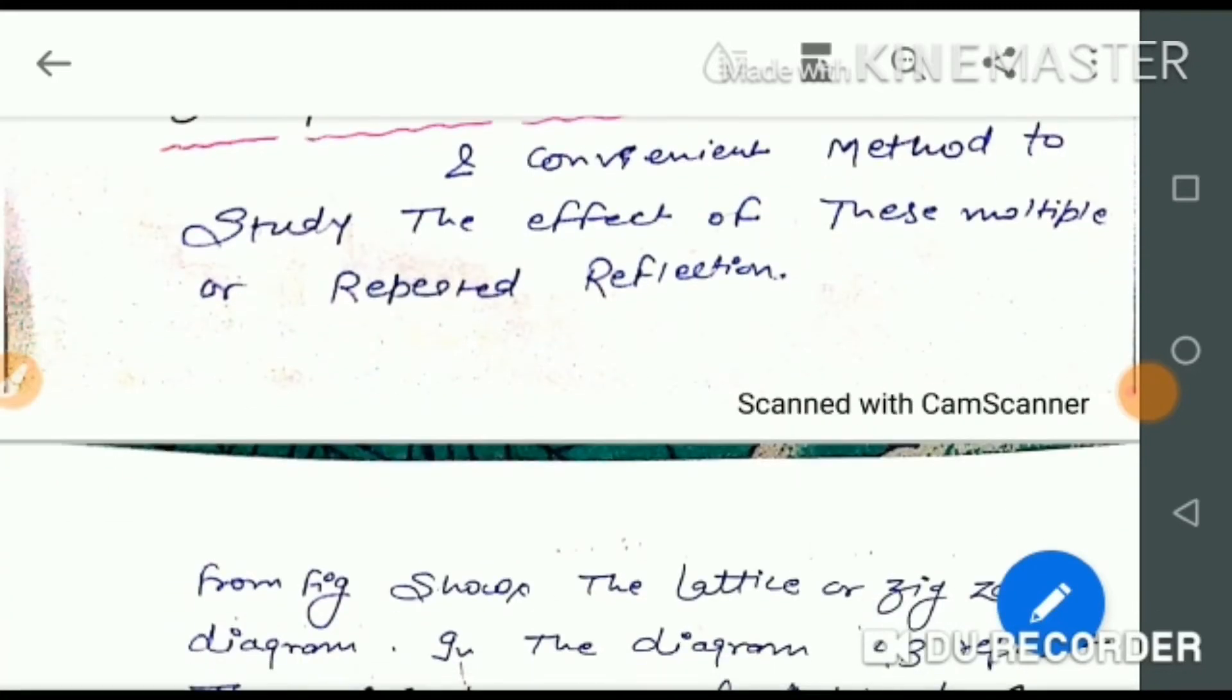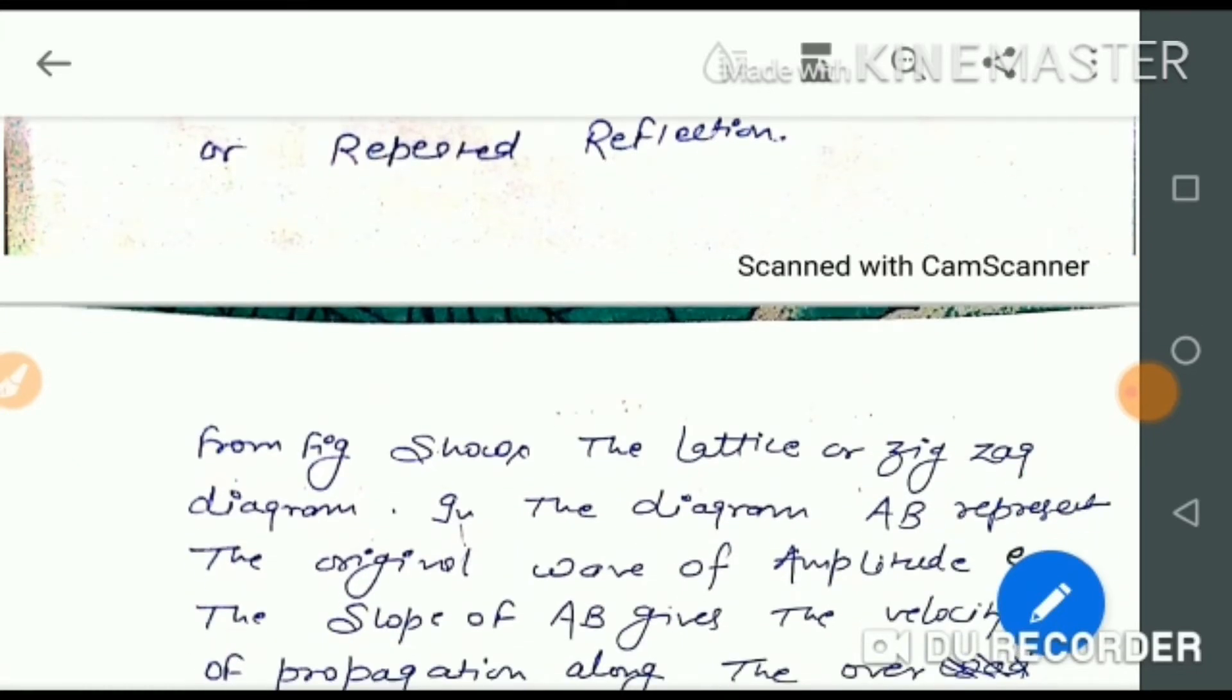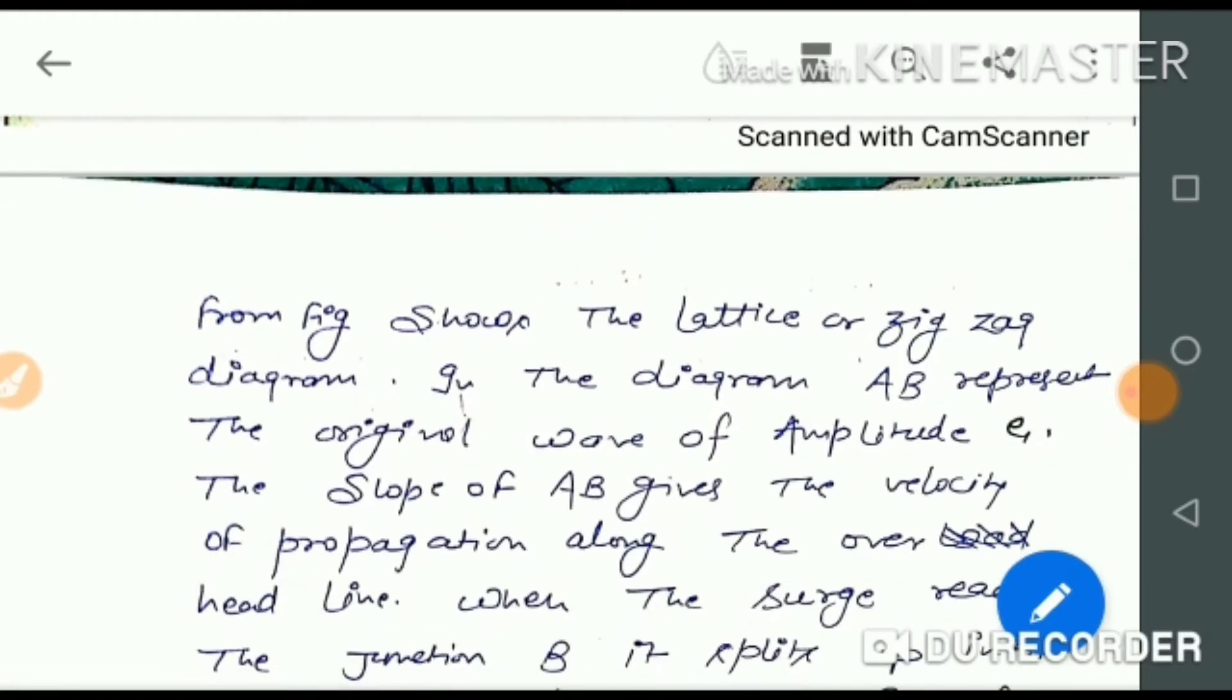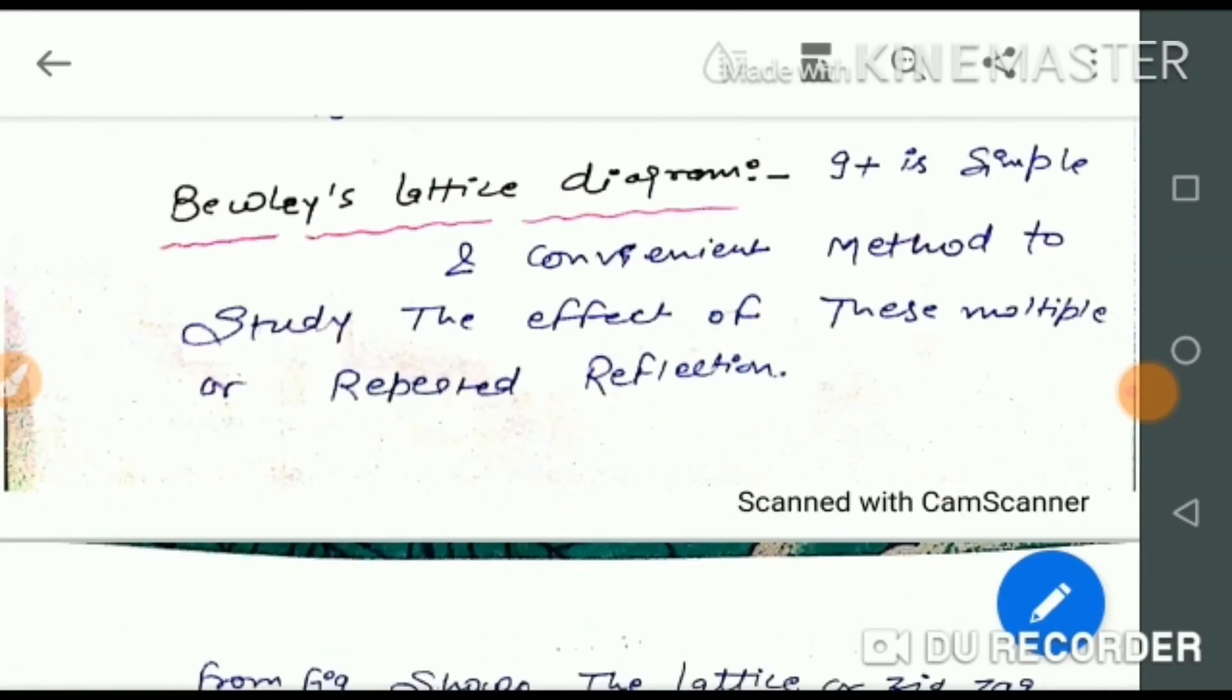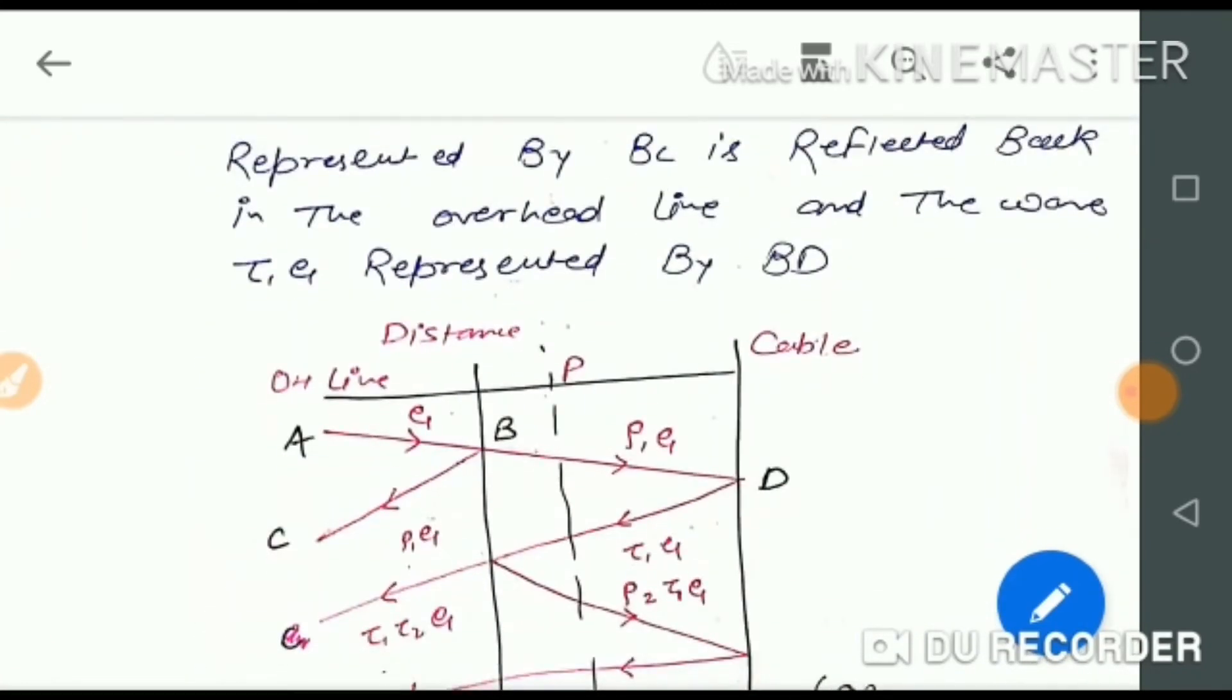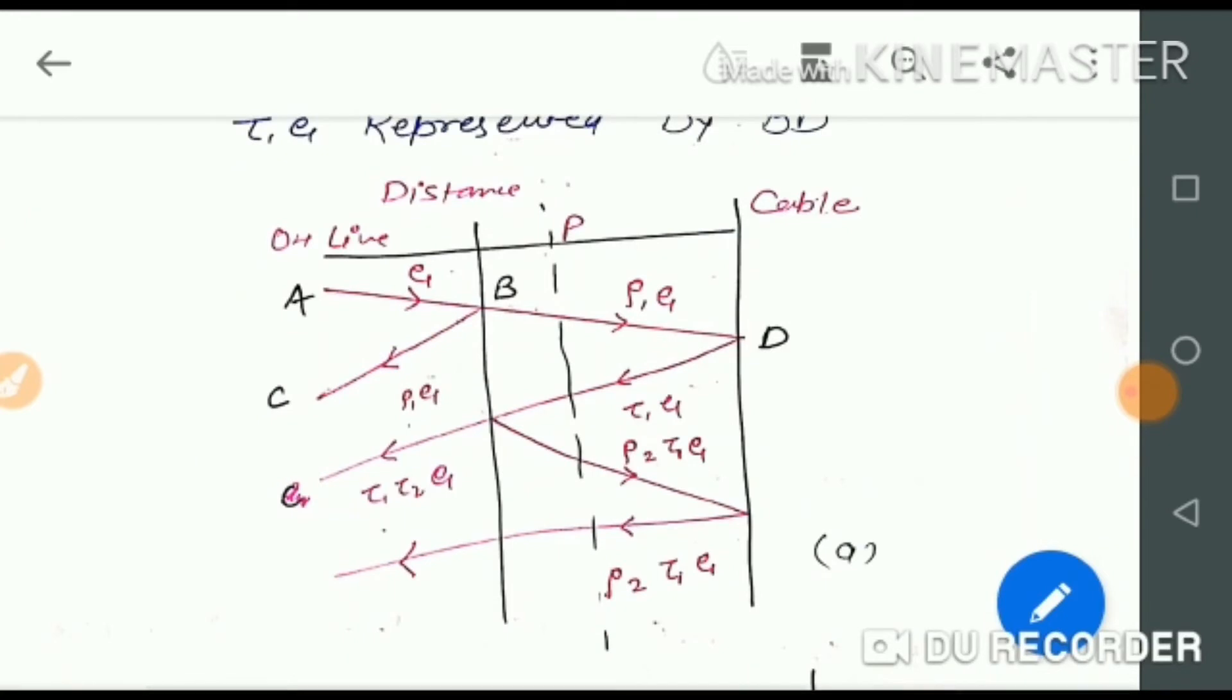It gives a picture of the position and direction of every incident, reflected, and transmitted wave on the system. The lattice diagram is a distance-time graph where the distance along the system and the direction of the original surge is taken.